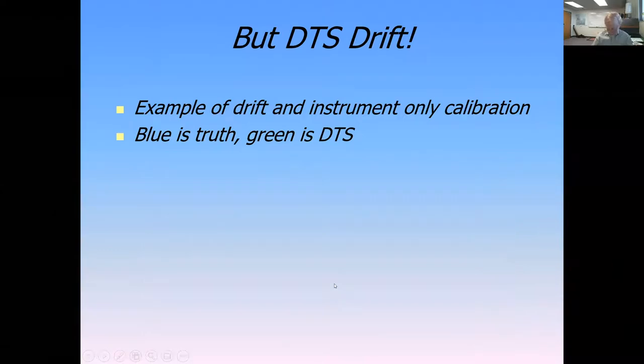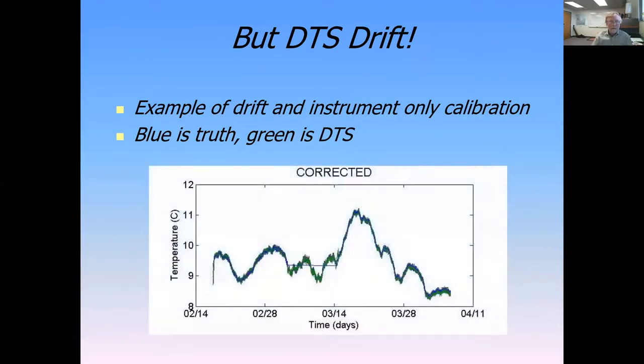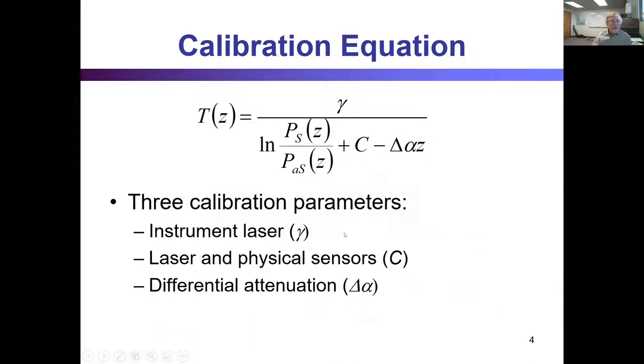With calibration, we can match these two and make sure that we are in the right spot all the time. So our calibration equation—this is a very simplified one—we are assuming that the differential attenuation along the optical fiber is constant in space, not necessarily in time. We can allow it to change in time, but it's going to be the same value all the way in space. And John just told you the idea of connectors are going to give us a variable attenuation in space.